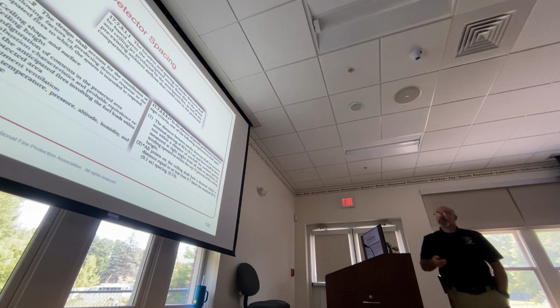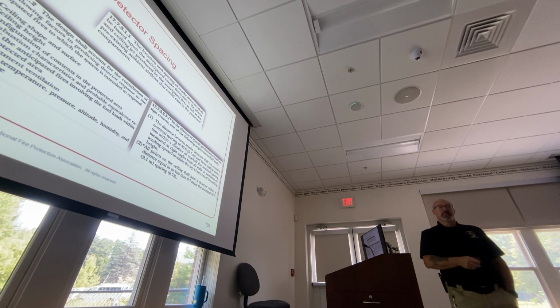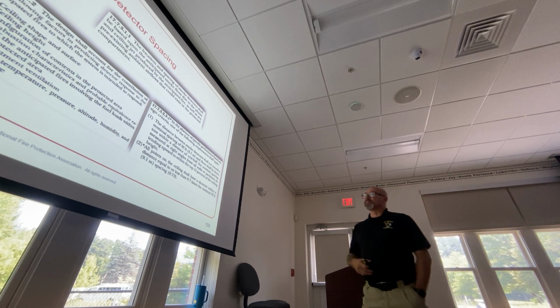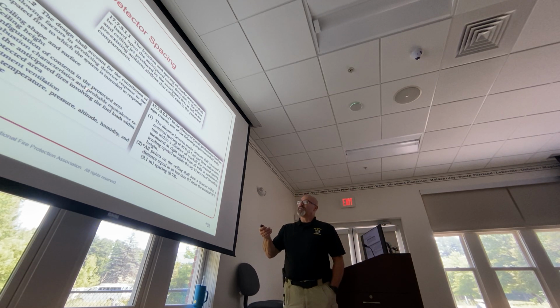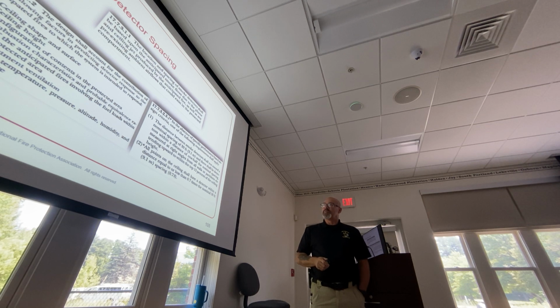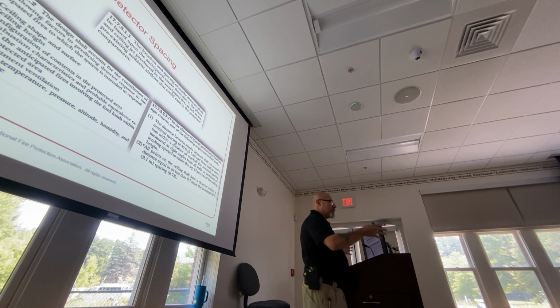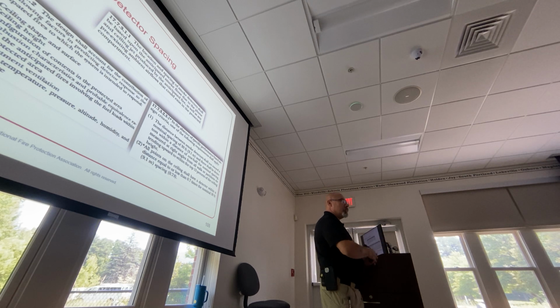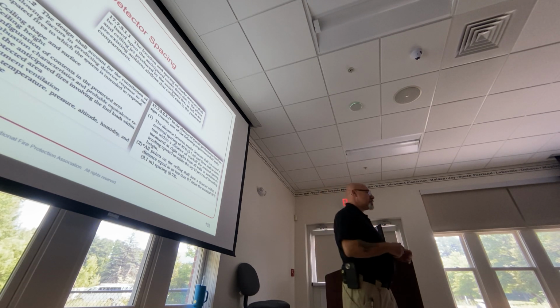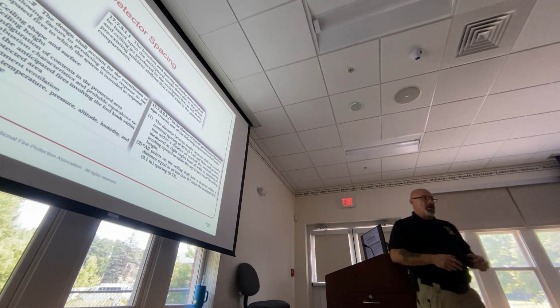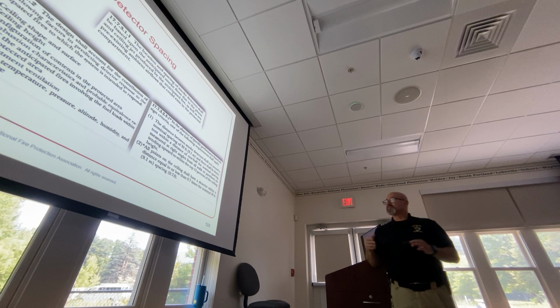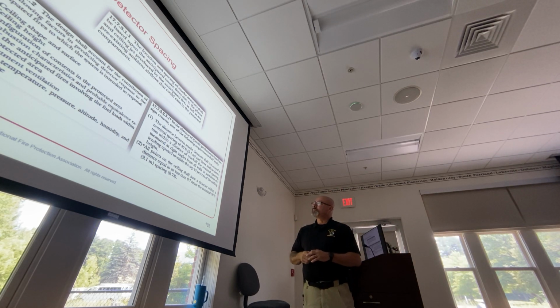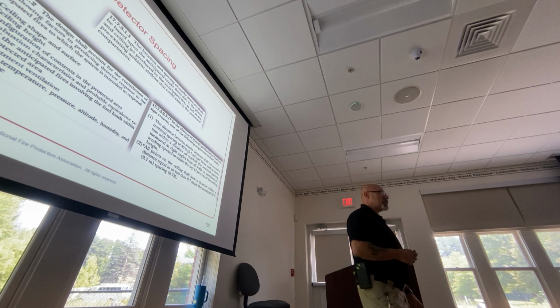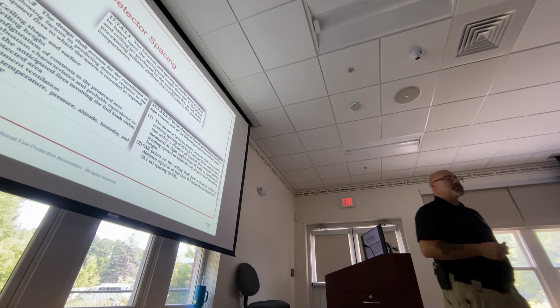Okay, so we have to anticipate the ceiling shape and surface when we're looking at installing these, the ceiling heights, the configuration of the contents in the protected area, combustion characteristics and probable equivalence ratio of the anticipated fires involving the fuel loads within the protected area. That's just saying that things can get very hot and very intense very quickly. So the detection needs to be placed and designed accordingly. Again, we're not sprinkler designers here, okay? But we have to understand some of these things. What edition is this NFPA 72? It's the 2016 edition.